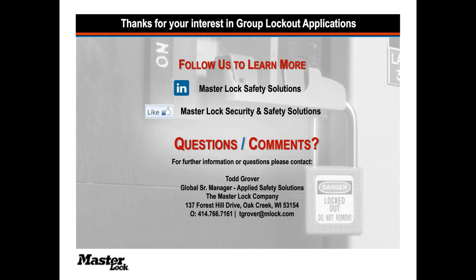All right, our next question. If my group box has 12 locks needed to isolate a piece of equipment, is it okay to have the 12 locks keyed alike to simplify? Would you place the master in the box and then each employee places their personal lock on the group box? That's exactly right. The 12 locks all keyed alike. There would be one key to 12 locks, and they would go on the machine, and then it becomes very easy to pick the one key to release all 12 locks versus 12 keys and then trying to get the order correct to release the locks.